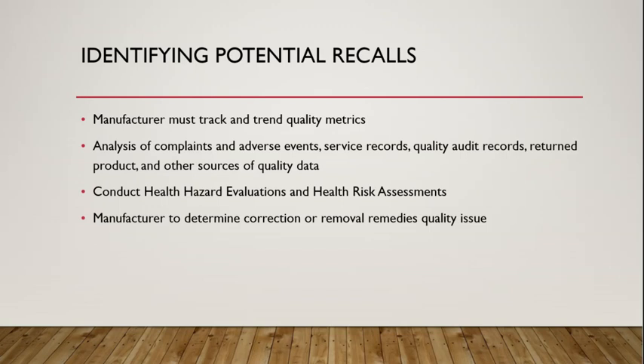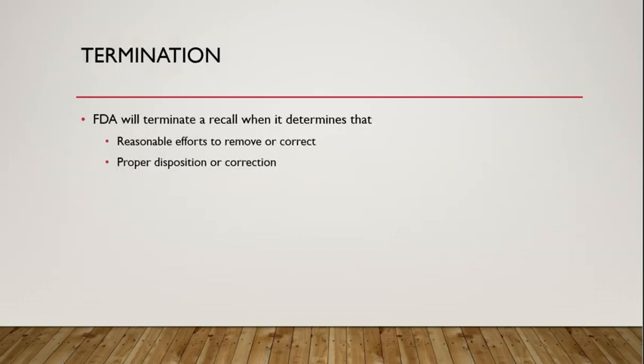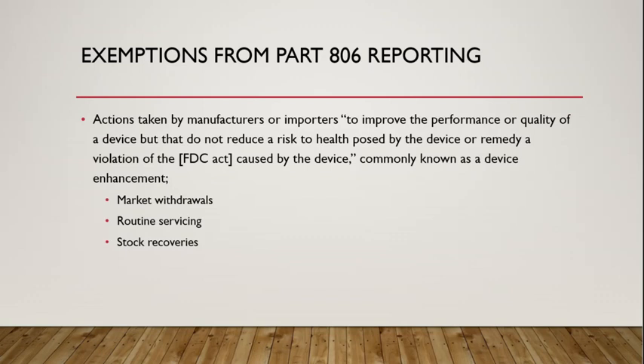FDA identifies potential recalls, and the manufacturers do, by tracking and trending metrics, looking at complaints and adverse events, service records. Manufacturers will conduct health hazard evaluations and health risk assessments, and manufacturers can determine and then implement correction or removal remedies if quality is the issue. An FDA recall will terminate when it determines that reasonable efforts to remove or correct have occurred and there's been proper disposition or correction. I want to close with a familiar theme in these lectures, and those are exemptions.